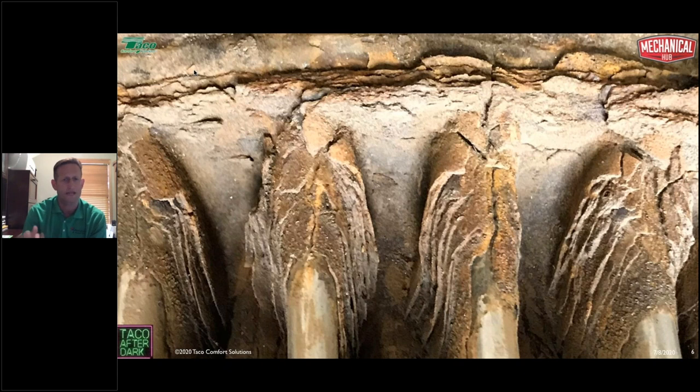If the condensate trap isn't cleaned and maintained annually, it can build up and start to short-cycle the boiler. There's no condensing boiler I know of that doesn't require maintenance. As you can see in this fire tube heat exchanger, the contaminants built up at the hottest point — up at the top where the burner fires down into the fire tube. That's where fire tubes typically fail, and it's not because of a bad weld — it's because of insulation from contaminants and overheating.